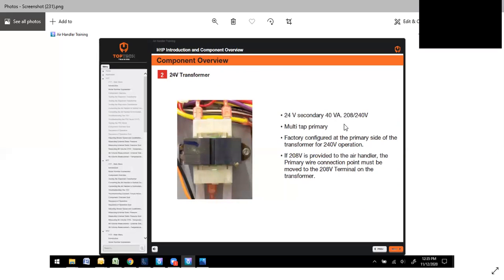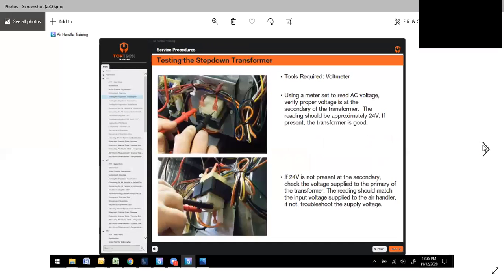It has a 24-volt 40VA, 208/240 multi-tap primary. So depending on whether you're using 208 or 230, you'll want to configure it as such. It's factory configured at 240 volts. If you're down at 208, make sure you move your terminal to the 208 terminal. Testing the transformer is pretty simple. If you have power to the unit, you want to check on the low side, the step down side here. If it's powered up and you do not have 24 volts there, you could have a bad transformer. But there again, you would want to check on the top to make sure that you have 240 into it. If you have 208 or 230 in, you should have 24 out.